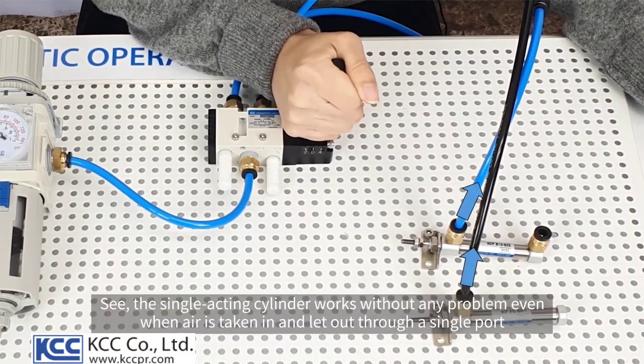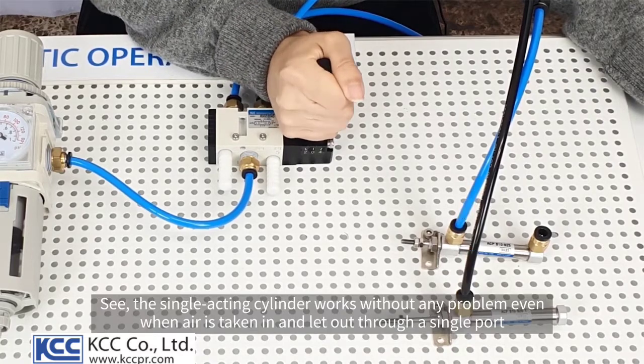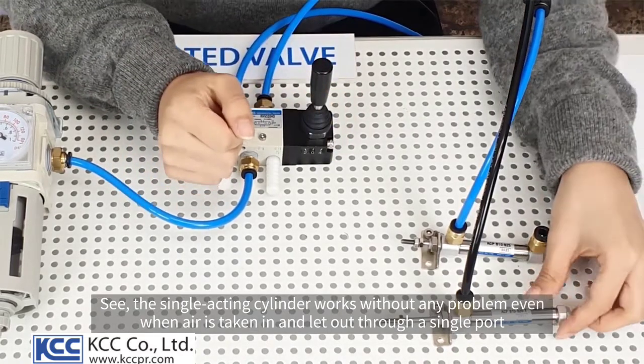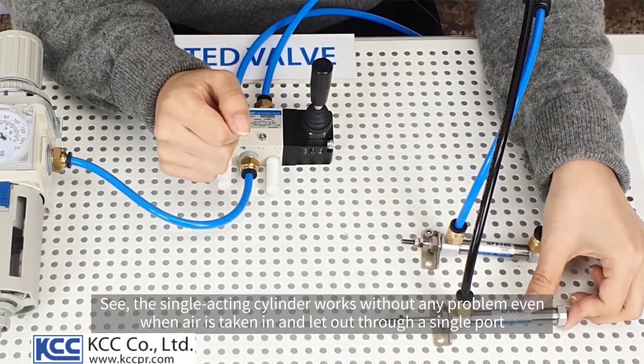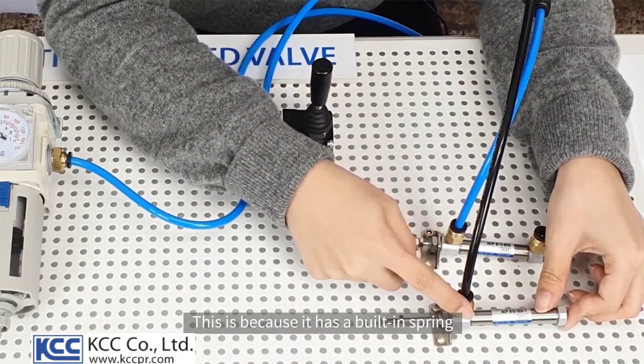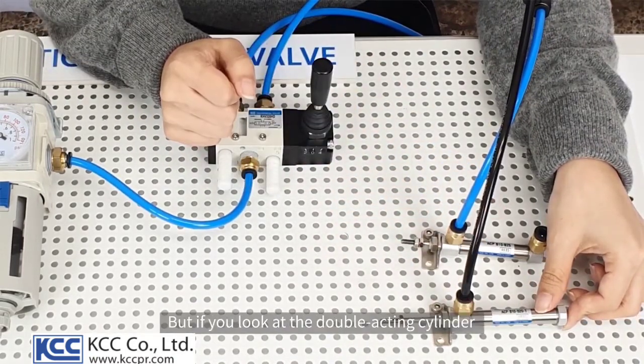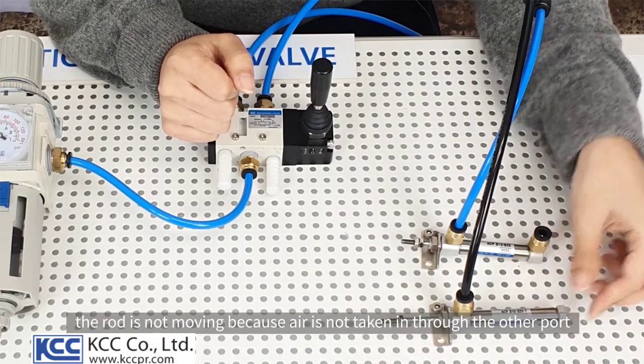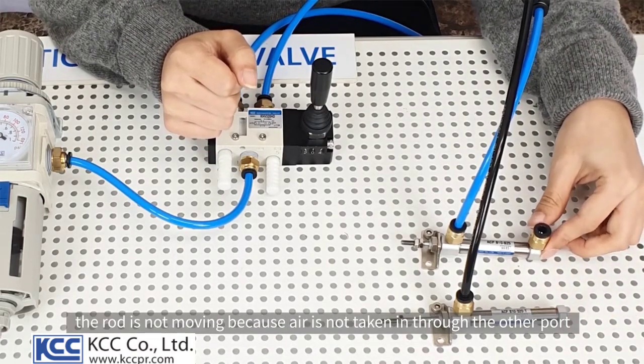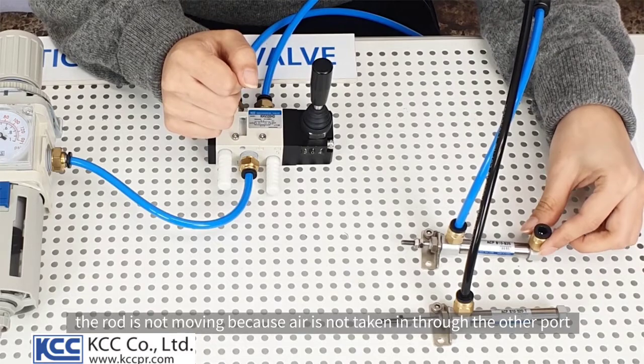See, the single-acting cylinder works without any problem even when air is taken in and let out through a single port. This is because it has a built-in spring. But if you look at the double-acting cylinder, the rod is not moving because air is not taken in through the other port.